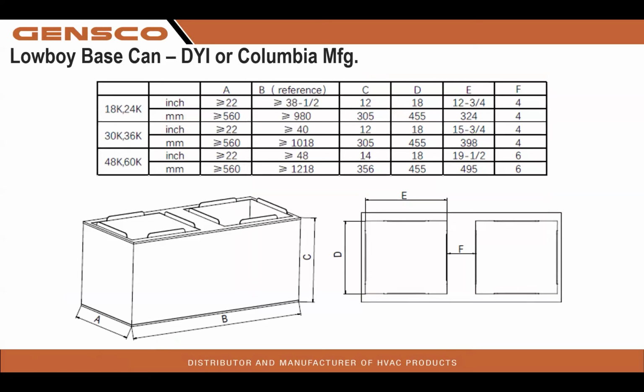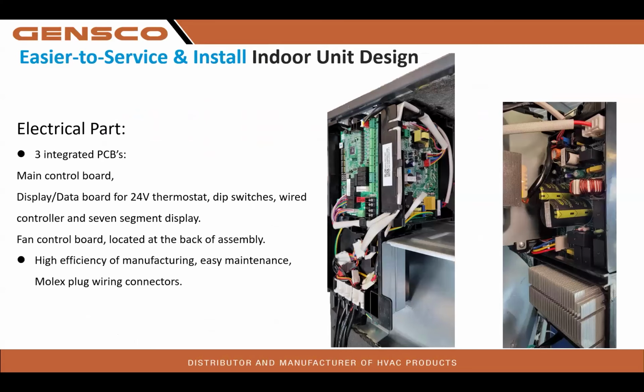So basically, we want the front of the equipment always to be the same. No mix match, don't spin it a different way. Low boy base can. You can either build it yourself or have Columbia Manufacturing build you one. There are the dimensions if you need the cut sheet on the build. Columbia Manufacturing already has these in the computer ready to hit go, and we can manufacture you one in short order. Easy to service and easy to install indoor unit design. 3 integrated PCBs: main control board, data display board, 24-volt dip switches, wired controller and 7-segment display right on the front. Fan control board is located on the back of the assembly right here. High efficiency of manufacturing, easy maintenance, Molex plug wire connections. Everything's plug and play.